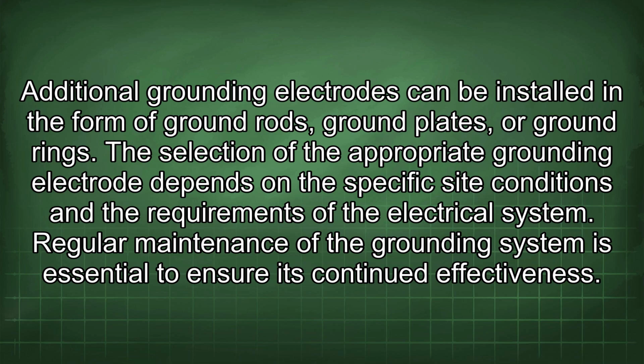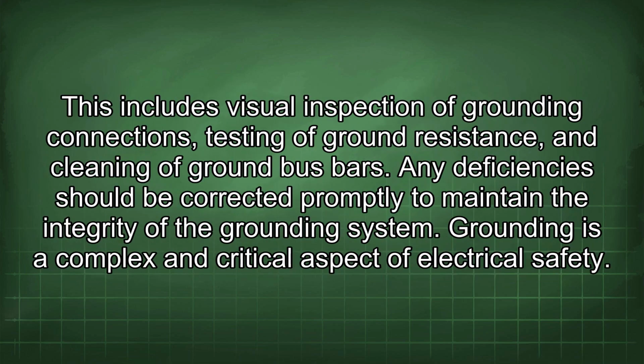Regular maintenance of the grounding system is essential to ensure its continued effectiveness. This includes visual inspection of grounding connections, testing of ground resistance, and cleaning of ground bus bars. Any deficiencies should be corrected promptly to maintain the integrity of the grounding system. Grounding is a complex and critical aspect of electrical safety.